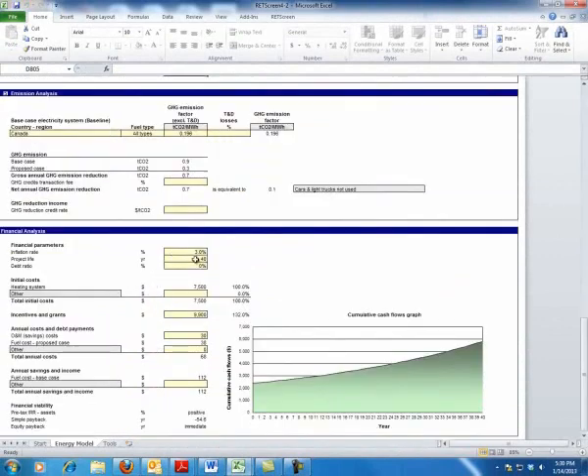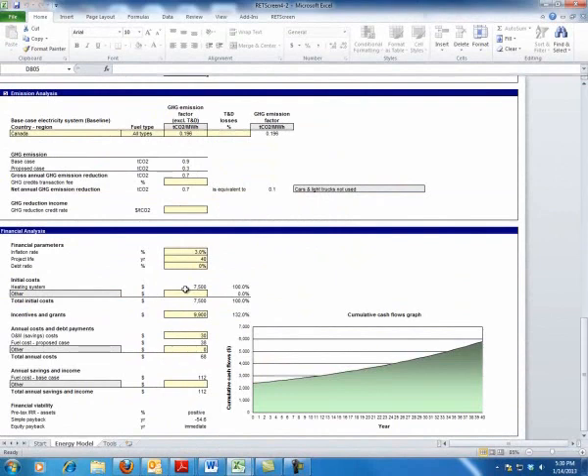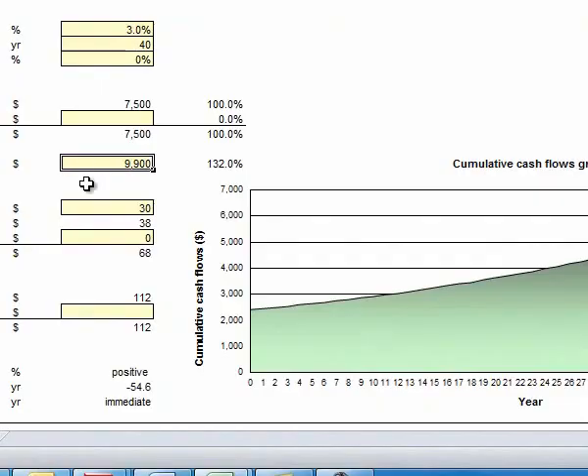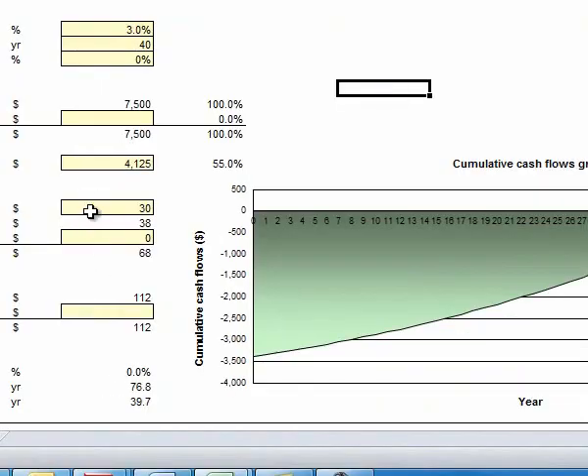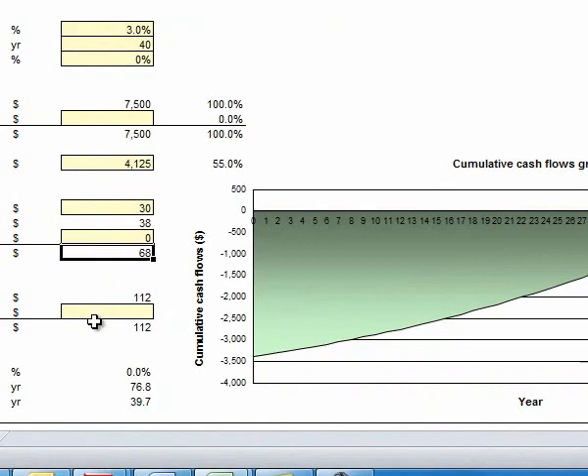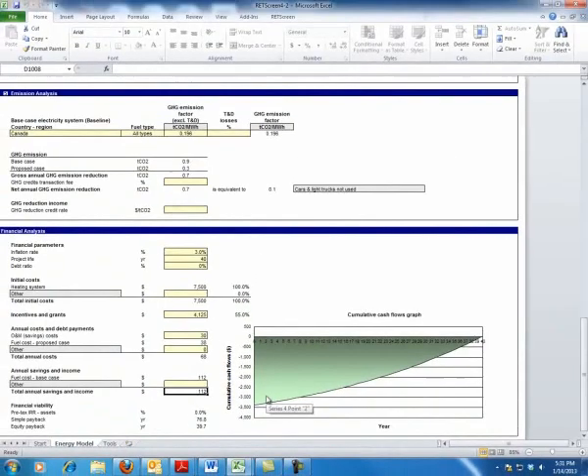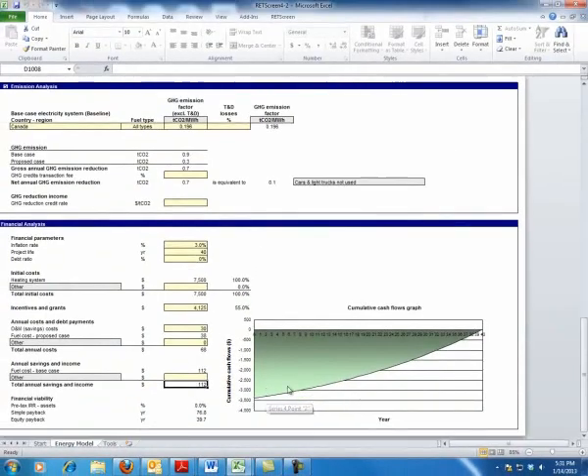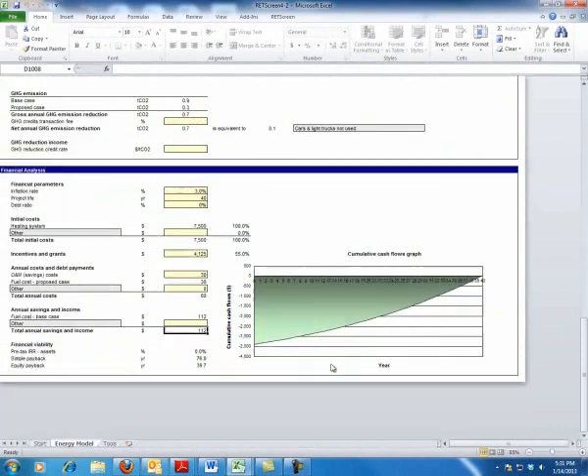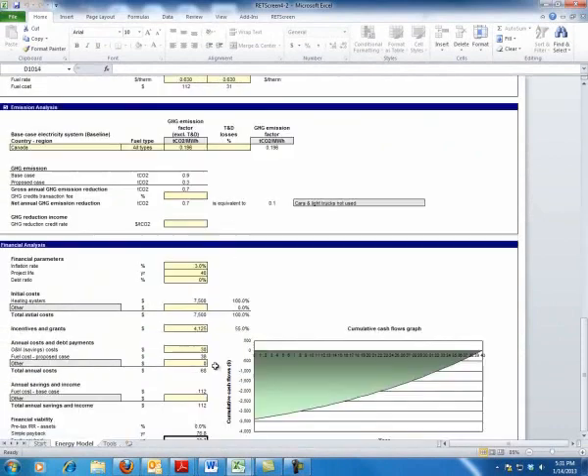Let's go back here. 40 years, it's 3%. Total cost is $7,500. Now, if I take that by the 55%, which is the cost savings of the 30% federal rebate and the 25% state of Illinois rebate, we get a rebate factor of $4,125. Now we've got some operating costs, annual costs, and we're going to save about $112 a year, but the payback is still going to be way out there right at 40 years.